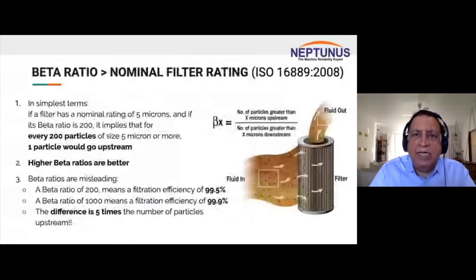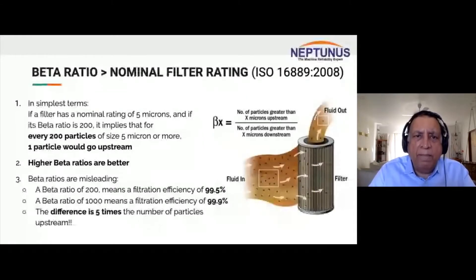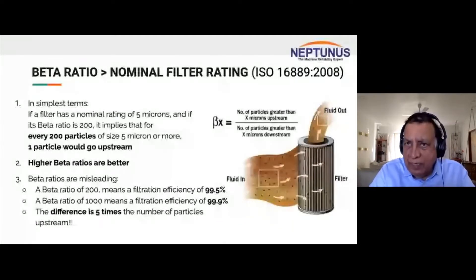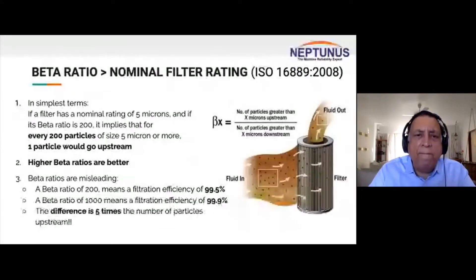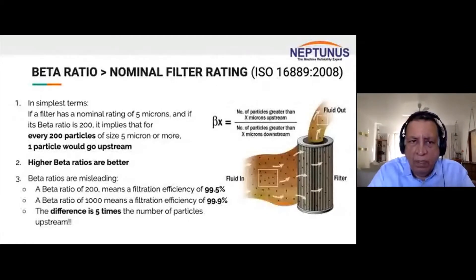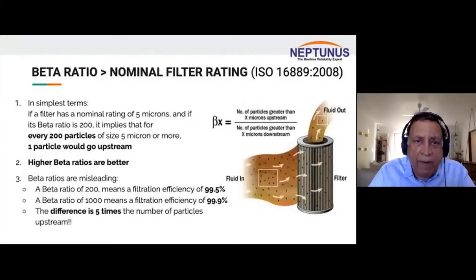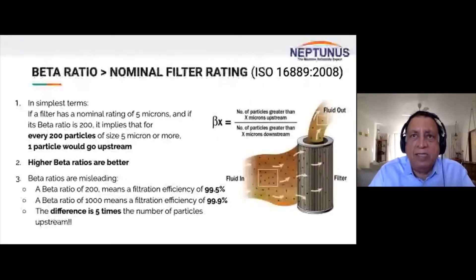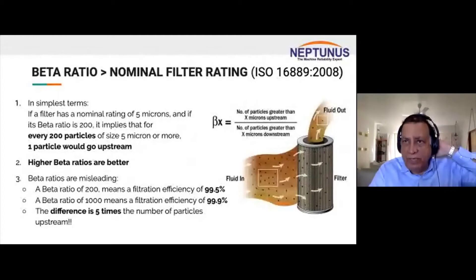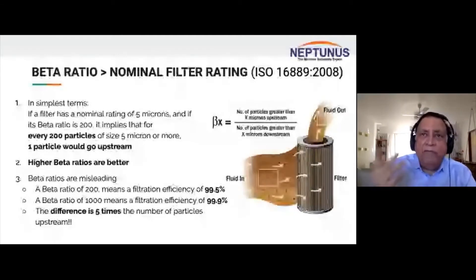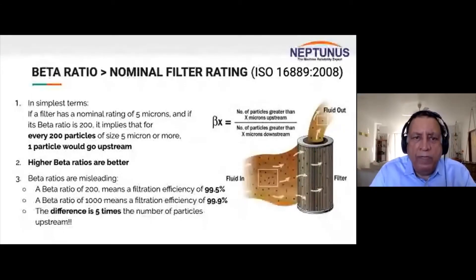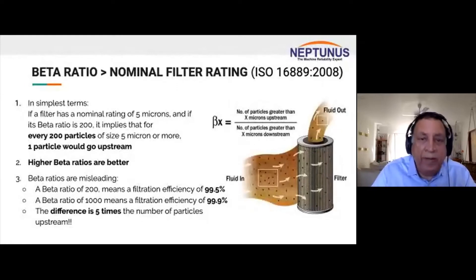Please understand the concept of beta ratio. If it's a 5 micron filter with a beta ratio of 200, it means that for every 200 particles of 5 micron or more, only one particle would pass through. A beta ratio of 950 means that for every 950 particles, only one particle passes through. Obviously, higher beta ratios mean better filtration systems.